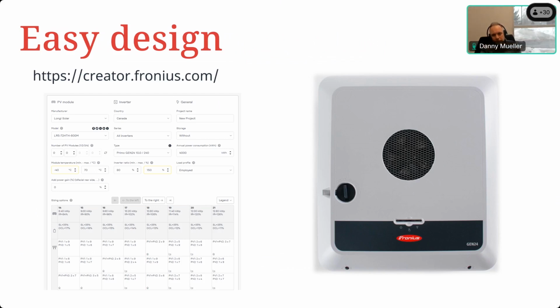but we would recommend that you use it for string sizing, that you calculate in some bifacial gains, because your voltage may get too high that way, and then you may damage the unit there. So you should always make sure when doing string sizing that you calculate in some bifacial gains. Is that correct? Exactly. That is correct.